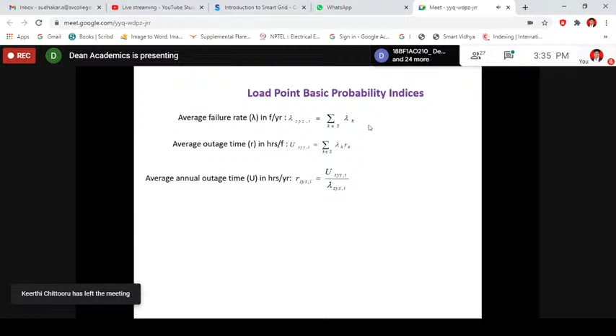For the exponential distribution, the equivalent failure rate equals the sum of the individual failure rates—that is how this formula arises. The rest follows the same formula and notation: average outage time equals sigma of lambda into R, and R equals U by lambda.